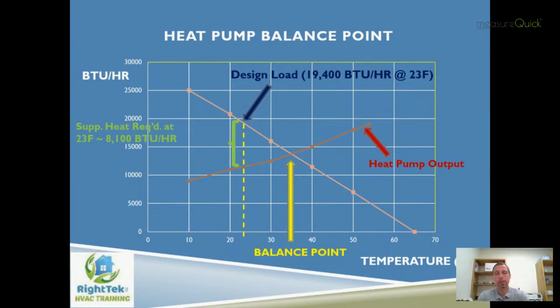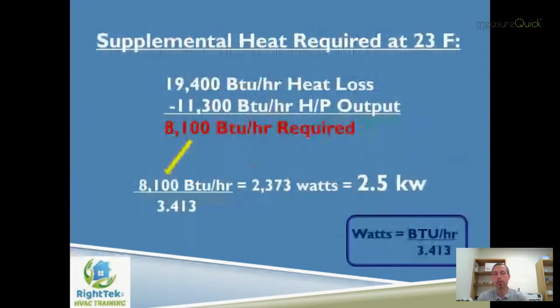So for this particular scenario, if I did the math, and I realize I'm accelerating through a lot of fine points here because we are limited on the amount of time we have, I would see that I've got to make up a gap between 35 getting down to my design of 23 degrees of approximately 8,100 BTUs per hour. And I need to figure out, well, what size heat strip would let me accomplish that?